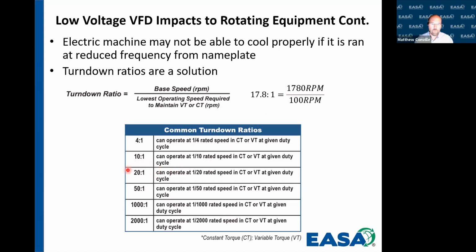So at a minimum, we would want to use a motor that is 20 to 1. We want it to have a greater ratio than what we need. As you get closer towards zero speed, having to maintain zero speed, just like we talked about needing to increase the PPR, the pulses per revolution on an encoder, we're going to want to increase the turn down ratio somewhere between 1,000 to 2,000 times. And these are just some common turn down ratios. You might actually see some motor manufacturers that give a 20-to-1 variable torque and a 10-to-1 constant torque, or they may both be the same. But the moral of the story is we really want to just pay attention to what turn down ratio is required for the application.